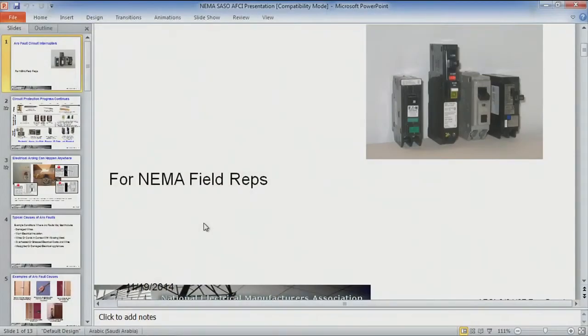But I also sent around an arc fault circuit breaker, which is what I'm talking about here today. The picture up here shows the arc fault circuit breakers that are available commercially in the North America market from each one of our competitors. Some of them are visually a bit different, but each one of them incorporates a self-test button so you can press and see whether or not the electronics in it are working properly. For the most part, they're the same kind of configuration. In some cases, there's an LED included that tells you what kind of trip has occurred in case you're trying to do some troubleshooting with the device.